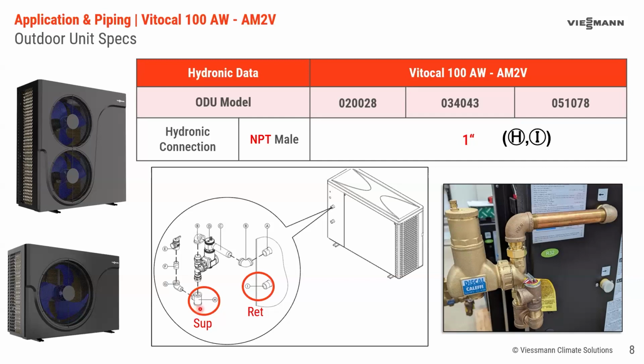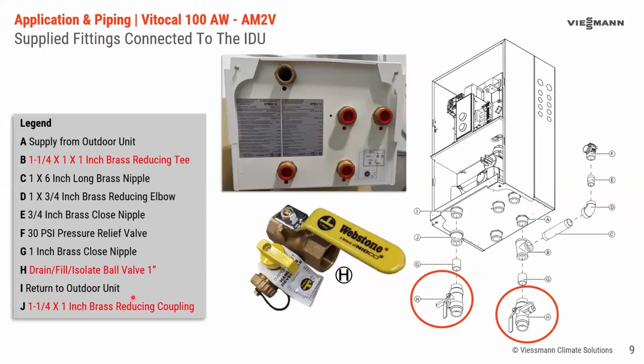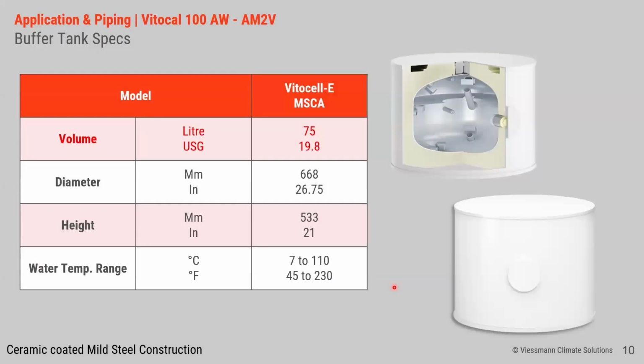And the indoor unit will be very similar. We're going to have inch and a quarter on the actual unit, but by the time we go through the adapters and valves, these isolation bypass valves that you see, these Webstone valves, everything's going to be 1 inch at the end of this. So it's important that you understand that we start out with 1 inch, and you may or may not be putting bigger pipe depending on how far you're going and what size of unit you're doing with. And again, they'll be covering that in future presentations.